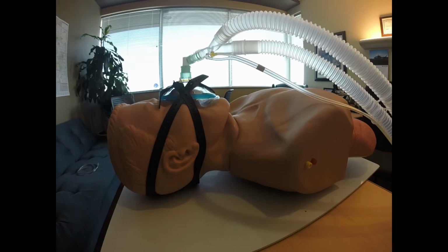When using the REVEL to do non-invasive positive pressure ventilation, you must attach the ventilator circuit to a face mask or a nasal mask. Only masks specifically labeled or intended for non-invasive ventilation should be employed on the REVEL ventilator. Masks should not have any valves or leak vents.